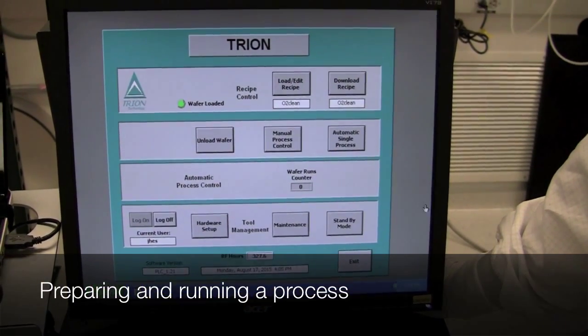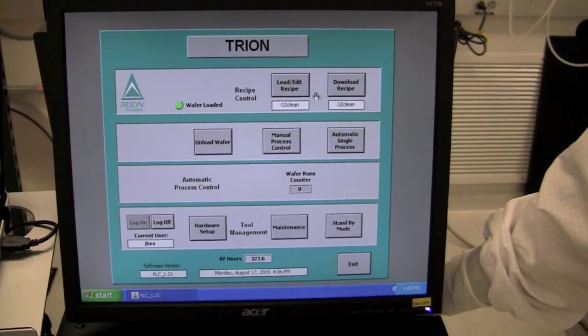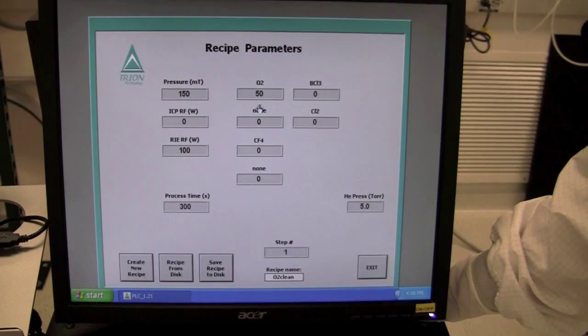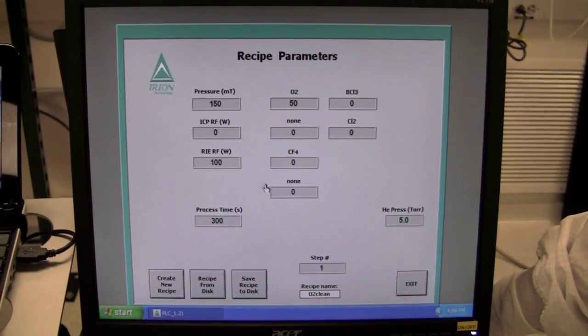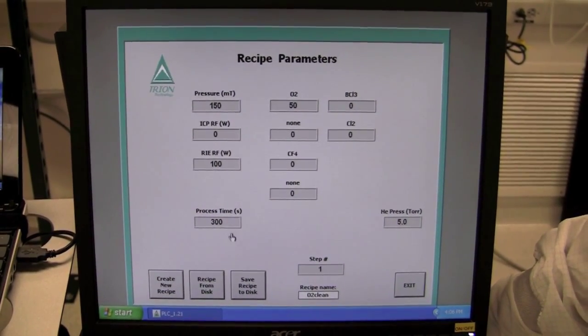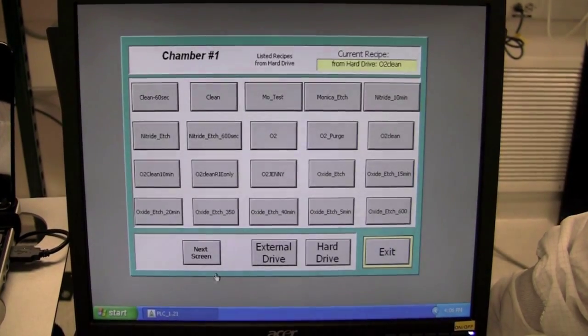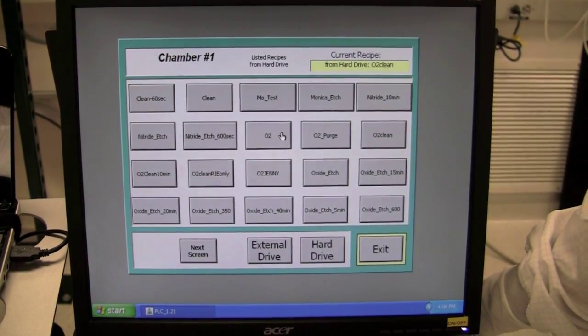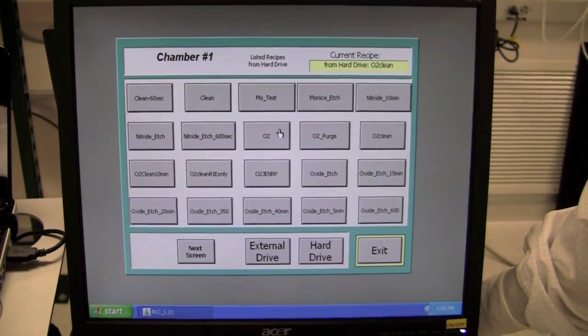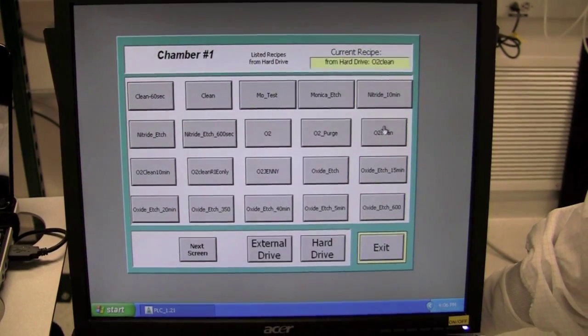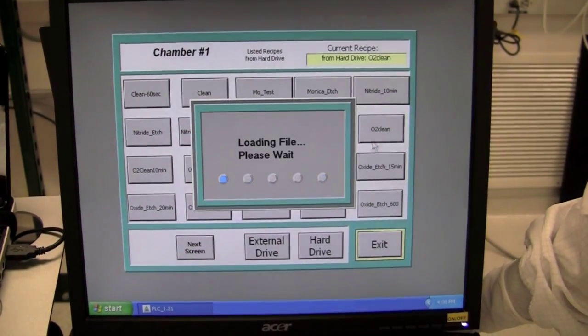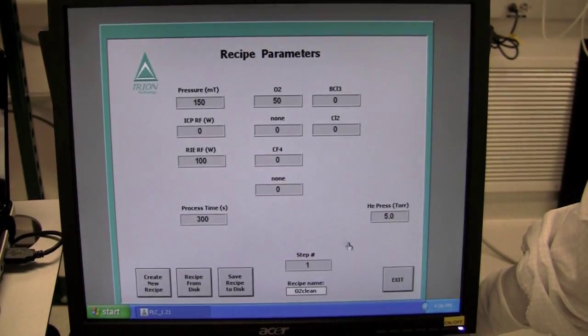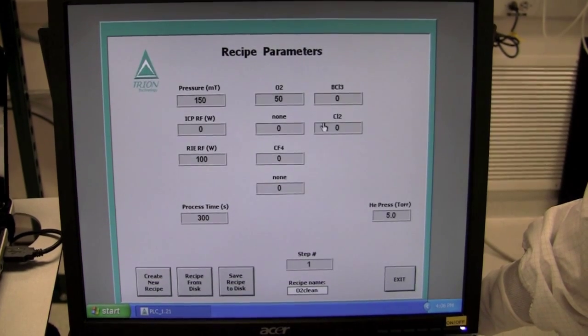To begin running the process, first you want to load a recipe. Under the top recipe control, you see a load edit recipe button. Click that and you see recipe parameters. Now, this happens to be O2Clean we just want to run but if you want to run a different recipe, what you do is click on recipe from disk and now you have a big series of recipes to pick from. Generally speaking, we only have about two or three most commonly recipes and the other ones are just variations on the process time. So, as before, we're just going to pick O2Clean, it will load the sample, hit exit, and now our parameters are loaded. They're going to be identical because it's the same recipe.